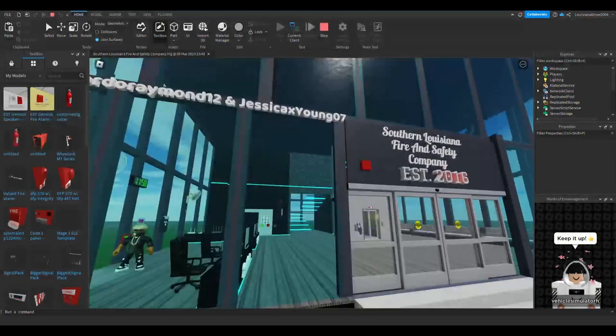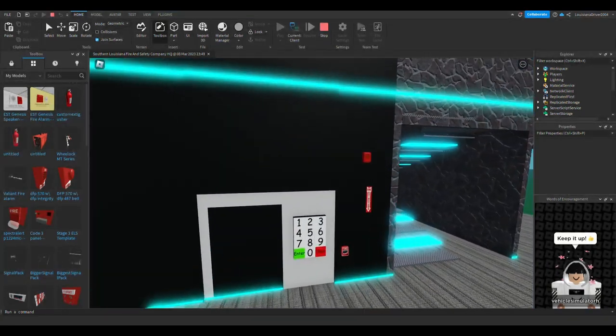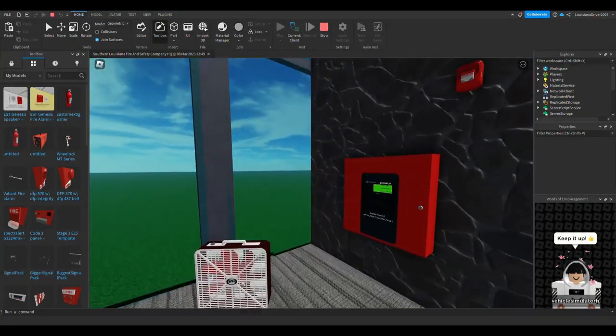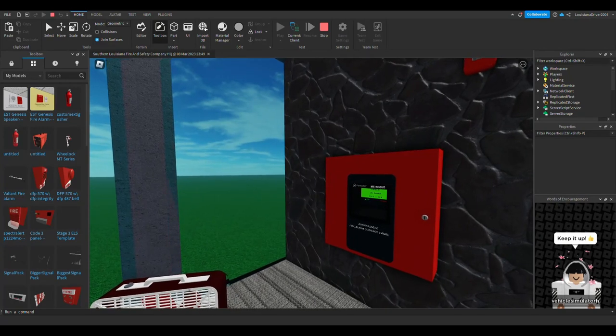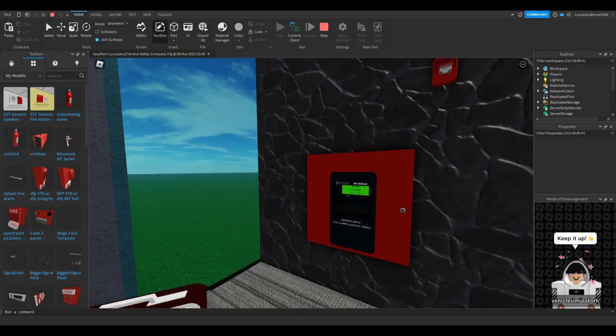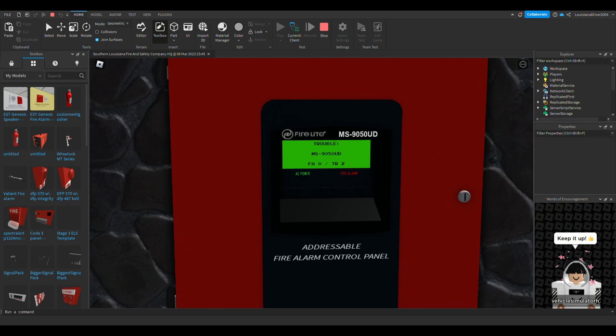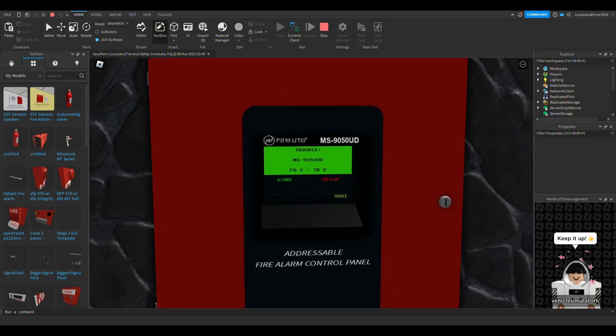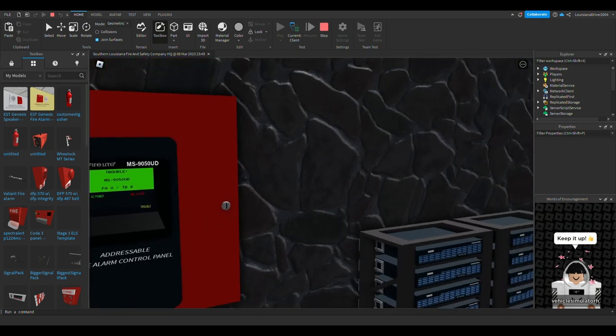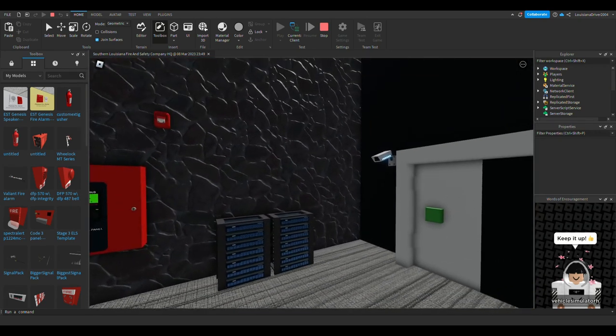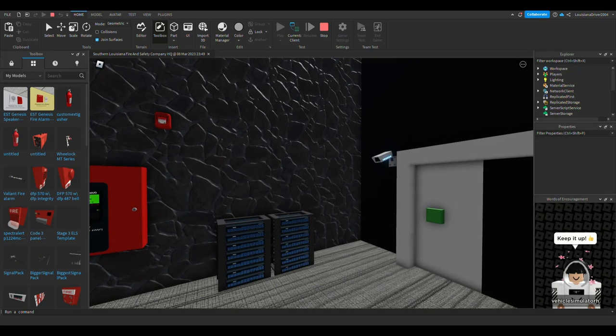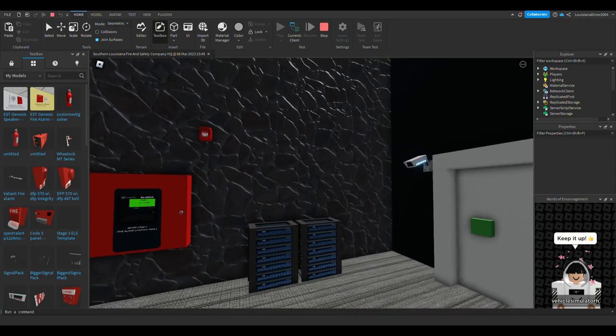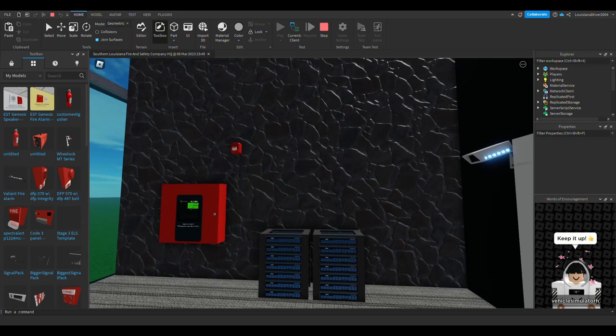So yeah, basically this system, I'm not going to get into depth, but nothing really changed. We're using the Fire-Lite MS-9050UD and as you can see there's already a couple troubles on the panel because of peripheral issues with the voice evac. Me changing the voice evac settings in the panel and the scripts kind of messes with that, so there is going to be a trouble that will be fixed.